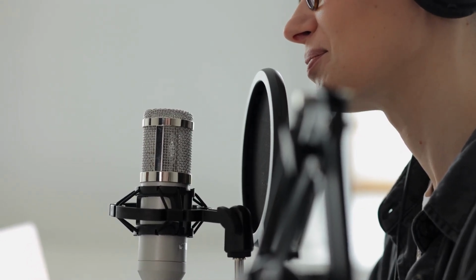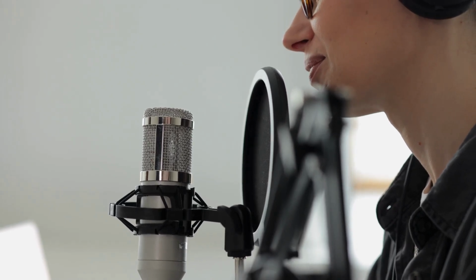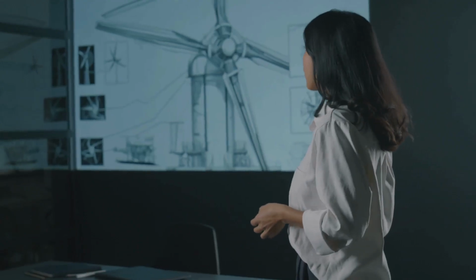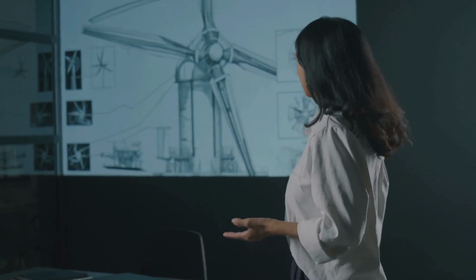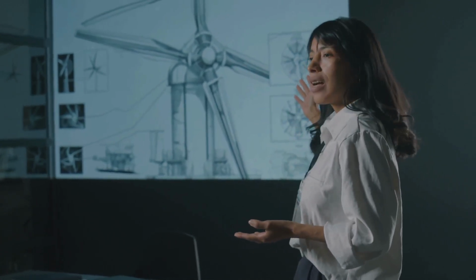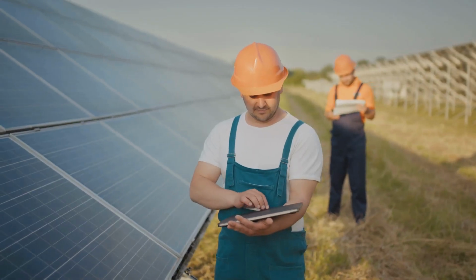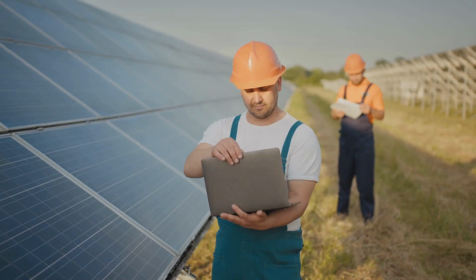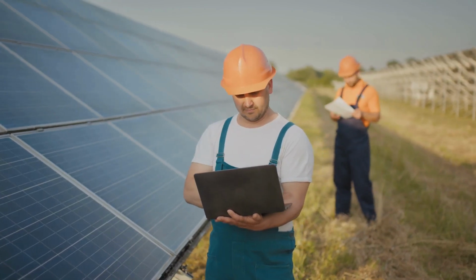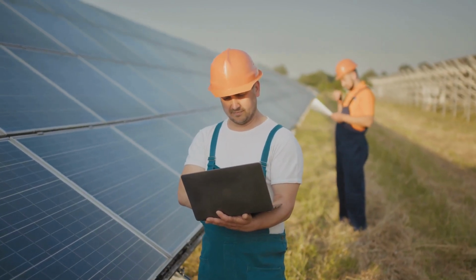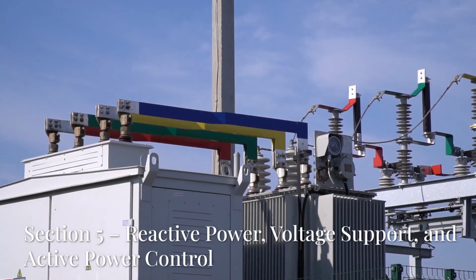Let's continue training on IEEE 1547-2018. In this segment, we focus on sections 5 and 6, where the standard introduces the active roles DERs must play in supporting the grid through dynamic control, especially under abnormal voltage and frequency conditions. This is where fault ride-through becomes not just a matter of staying online, but of contributing intelligently, proportionally, and dynamically to system stability during faults.